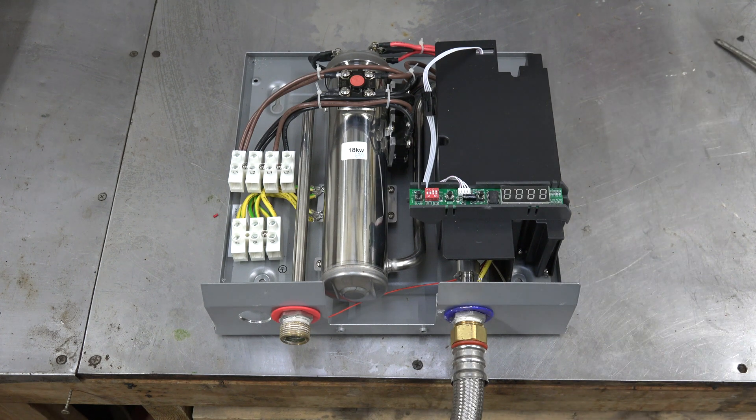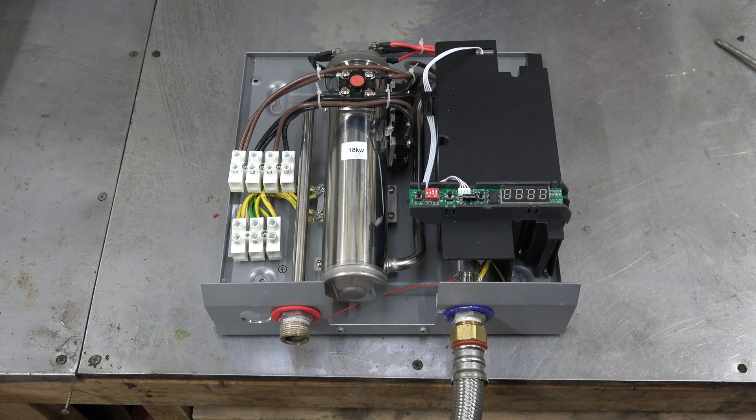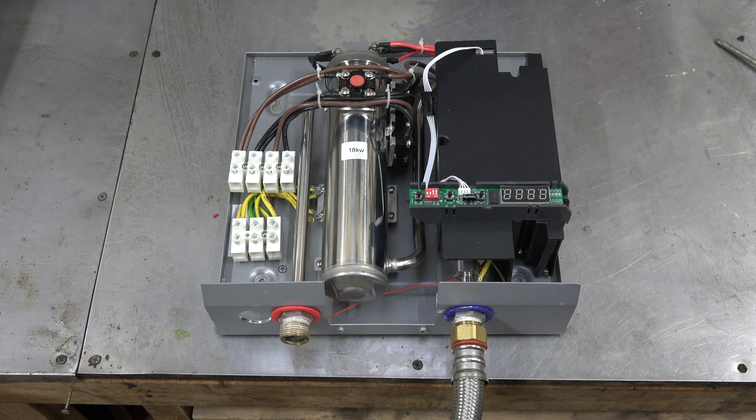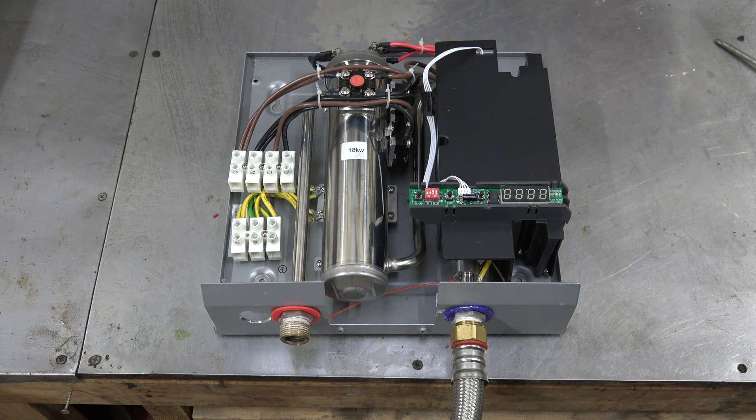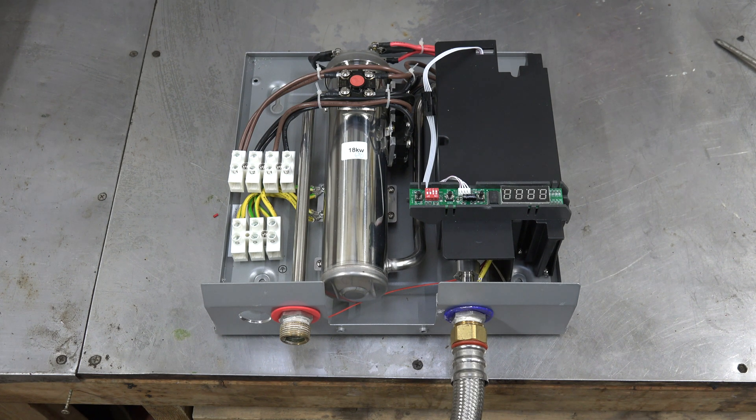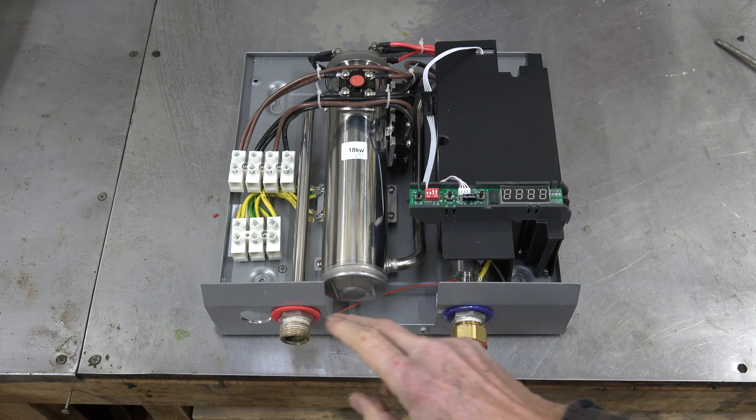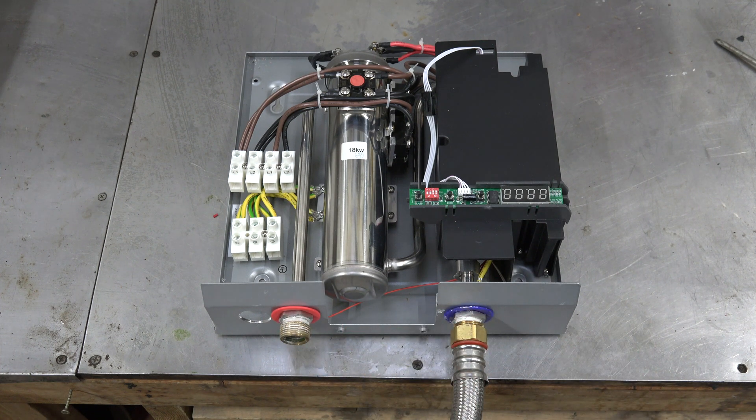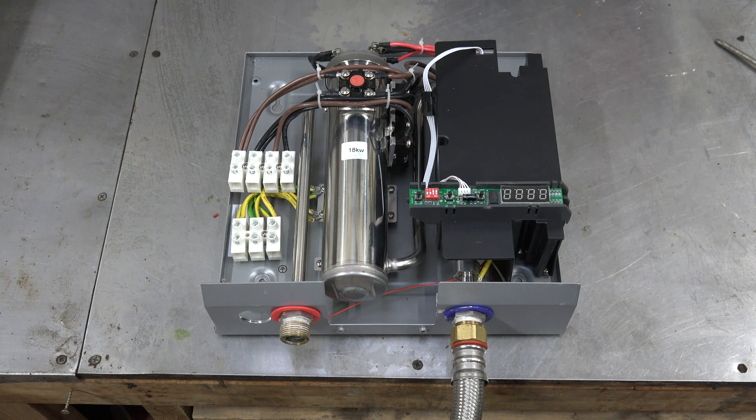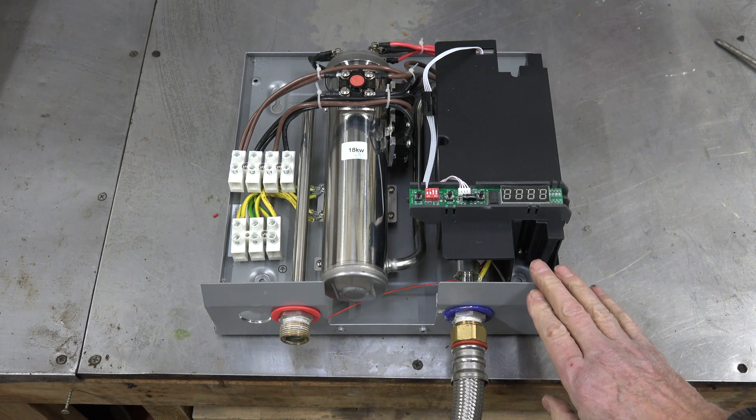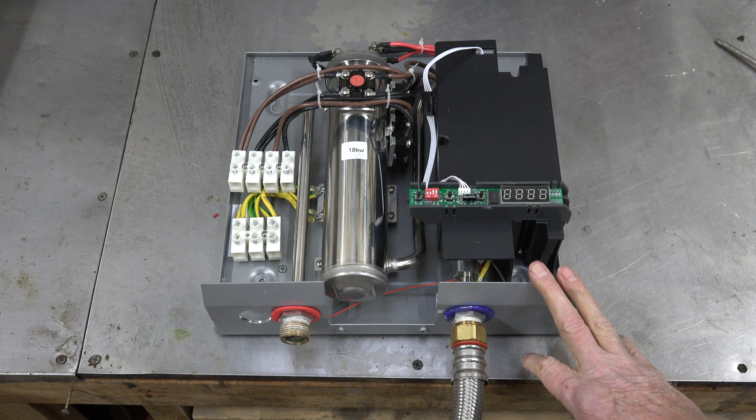This thing failed. When I first saw that it had stopped working, I thought it was possibly because one of the flow sensors had failed. There's a couple of flow sensors in here. They allow the thing to turn on when the water is running, because you can't have it on when the water's not running because there's no tank here, there's just water running through.